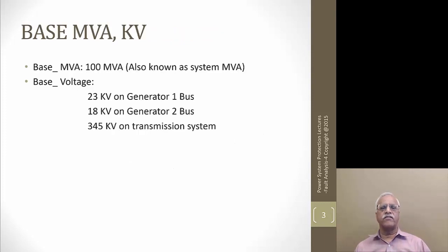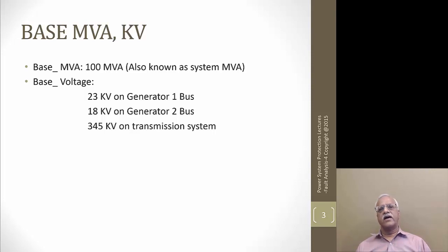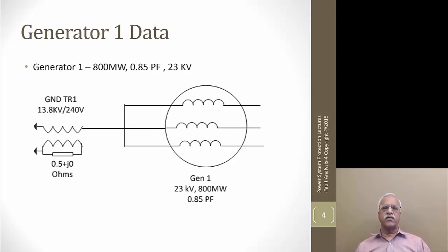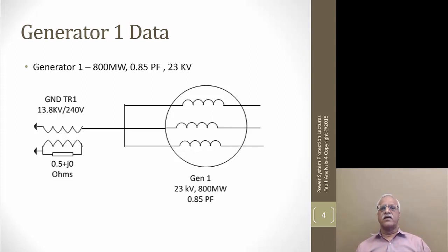Now if we look at the data, we will first determine what should be our base quantities. We assumed the base MVA as 100 MVA, also called the system MVA. The base voltage on the 23 kV side at generator one is 23 kV, for generator two it is 18 kV, and the transmission system is 345 kV. Generator one data: it is 800 megawatt, 0.85 power factor, generating at 23 kV.